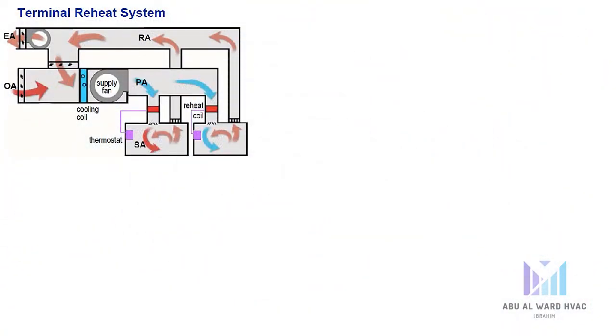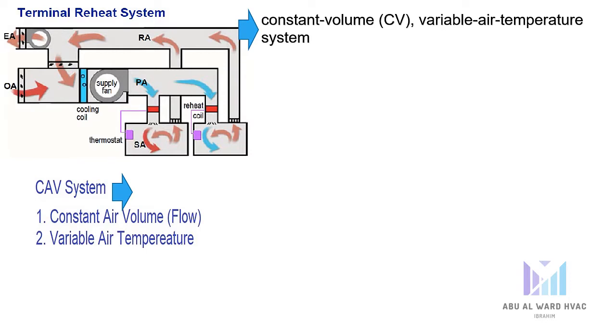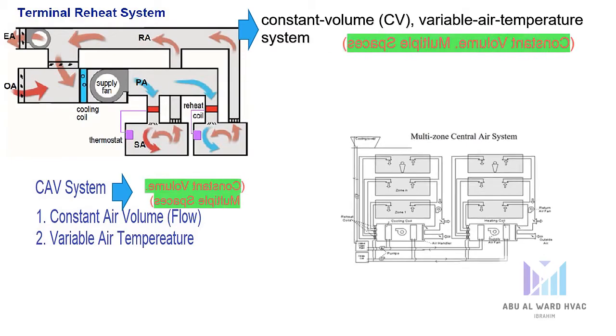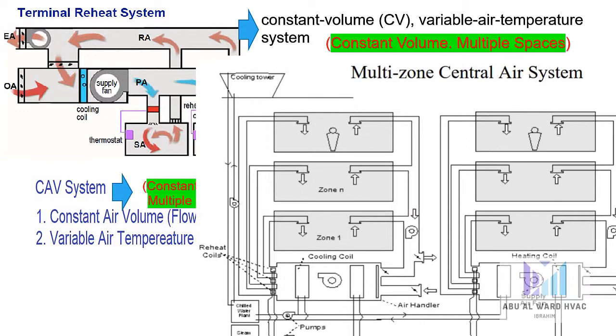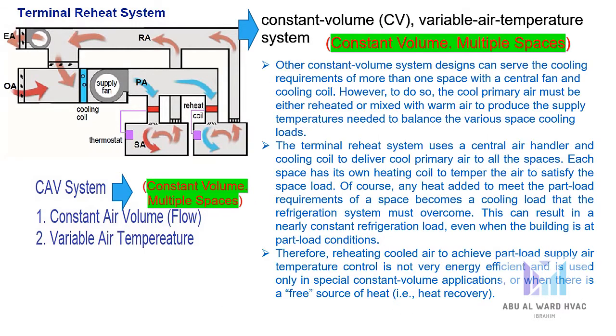Next we have the terminal reheat system, which is the same as a normal CAV except that it can serve multiple spaces with constant volume. This system design can serve the cooling requirements of more than one space with a central fan and cooling coil. However, to do so the cool primary air must be either reheated or mixed with warm air to produce the supply temperatures needed to balance the various space cooling loads. The terminal reheat system uses a central air handler and cooling coil to deliver cool primary air to all spaces, and each space has its own heating coil to temper the air.